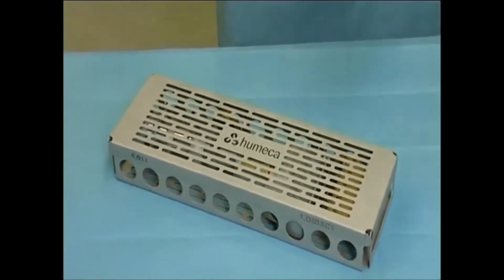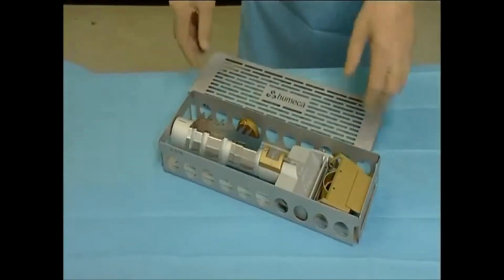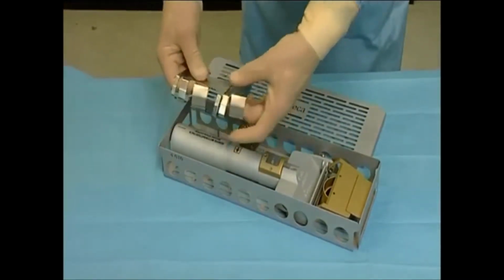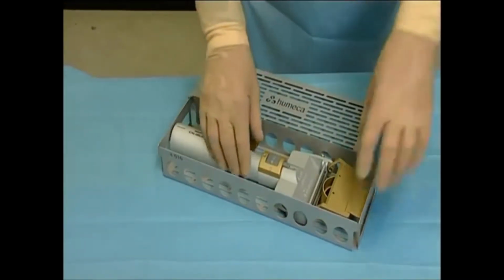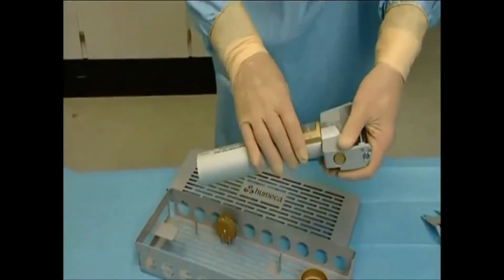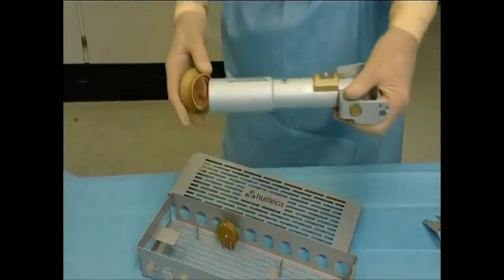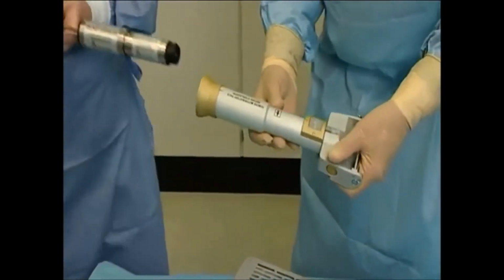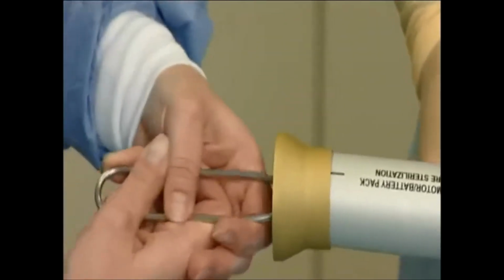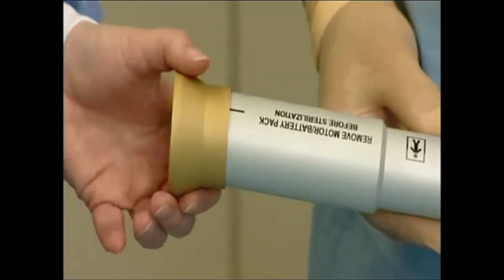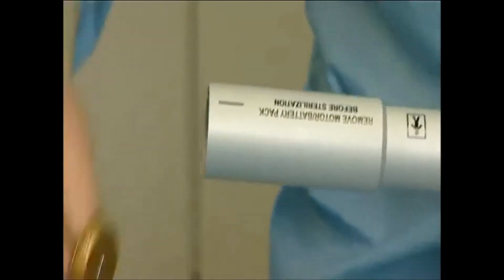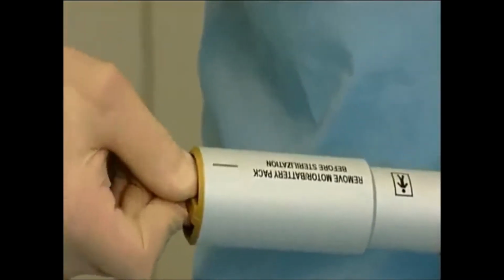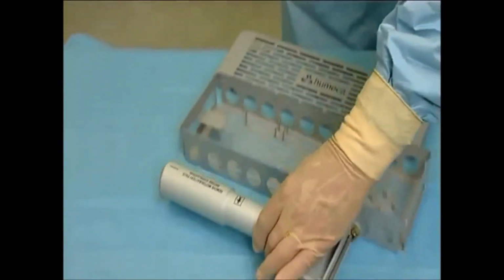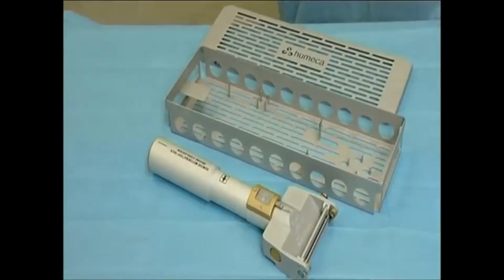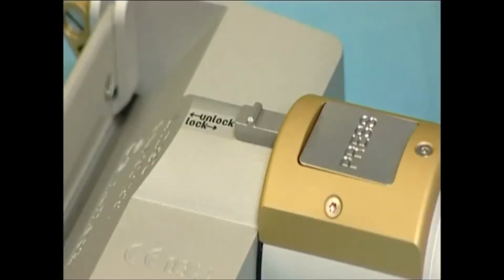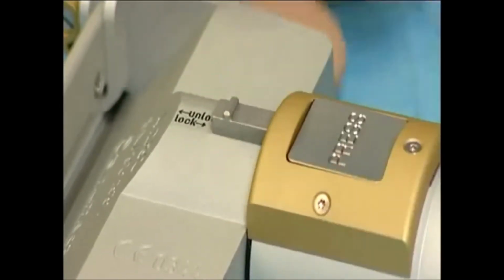Before use, the autoclave case is opened and the dermatome and its accessories are taken out. The blade cover is closed and a sterile funnel is slid over the open end of the shaft. After connecting them, the non-sterile motor and battery are slid in the shaft, guided by marking lines, while the sterile funnel prevents contamination of the outer surface. When the cartridge is completely inserted in the shaft, the open end is closed with a rear cap. For safety reasons, the dermatome is provided with a locking mechanism that prevents accidental run.